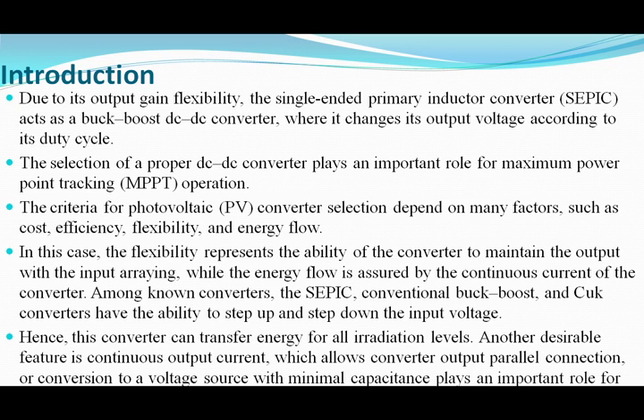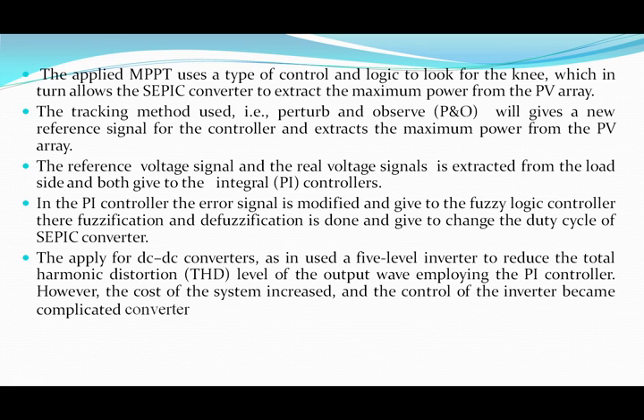The selection of a proper DC-DC converter plays an important role for maximum power point tracking. The criteria in selection of a PV voltage converter depend on many factors such as cost, efficiency, flexibility, and energy flow. Flexibility represents the ability of a converter to maintain outputs with the input varying, while energy flow is assured by the continuous current of the converter. Among known converters, SEPIC, the conventional buck-boost converters have the ability to step up and step down input voltage. The applied MPPT uses a type of control logic to look for the knee point, allowing the SEPIC converter to extract maximum power from the PV array. The tracking method is the Perturb and Observe method.